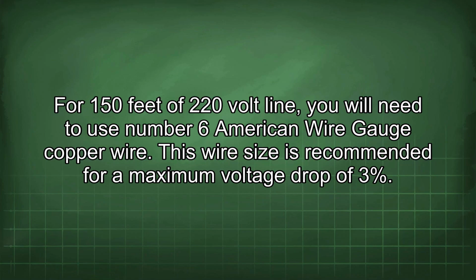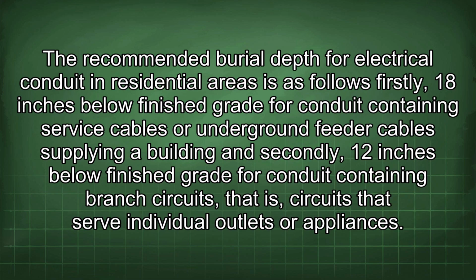For 150 feet of 220 volt line, you will need to use number 6 American wire gauge copper wire. This wire size is recommended for a maximum voltage drop of 3%. The recommended burial depth for electrical conduit in residential areas is as follows. Firstly, 18 inches below finished grade for conduit containing service cables or underground feeder cables supplying a building, and secondly, 12 inches below finished grade for conduit containing branch circuits, that is, circuits that serve individual outlets or appliances.